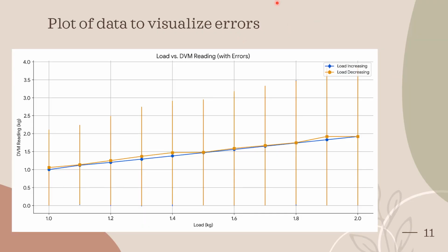We have plotted the data to visualize our errors. We can see on the y-axis we have digital voltmeter readings, which is in kg, and on the x-axis we have the load applied on the cantilever beam in kgs too. Ideally speaking, we expect a linear graph, but we can see there is not a linear graph. Also, we can see there are two lines. The blue line corresponds to the load increasing value, and the yellow line corresponds to the load decreasing value.